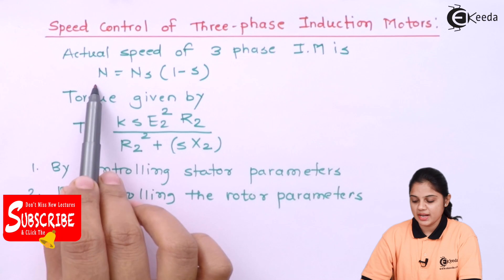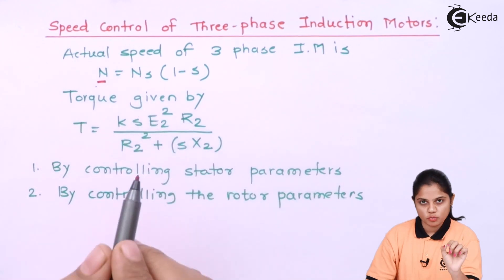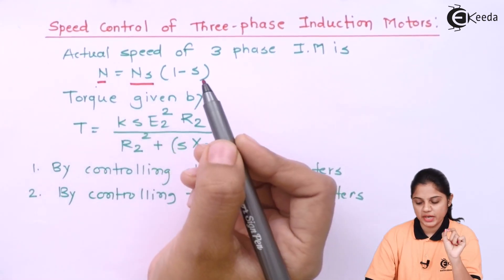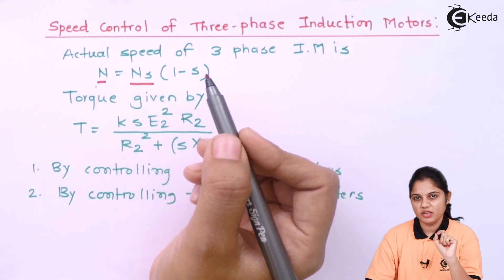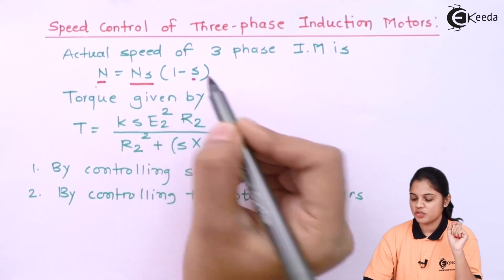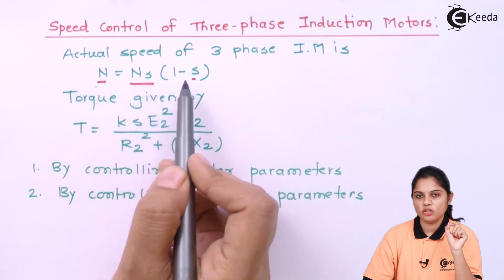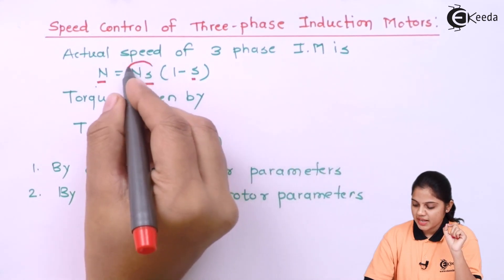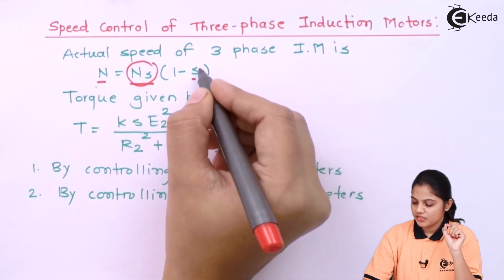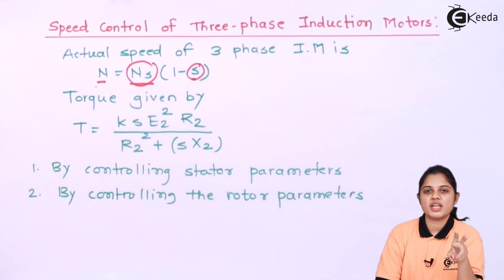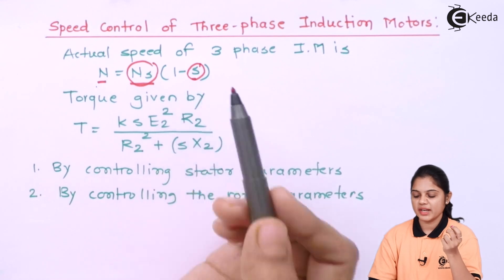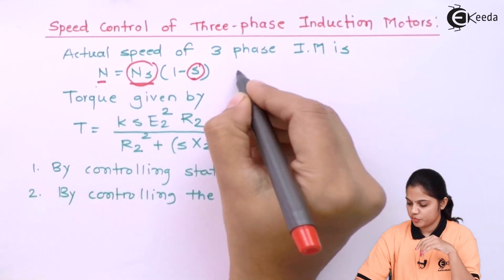The actual speed of the three-phase induction motor is given by: N = NS × (1 - S), where N is the speed of the motor, NS is the synchronous speed — that is 120F1 divided by P — which we have seen in a previous video, and S stands for slip. Now if you see the formula properly, either you can change NS, the synchronous speed, or you can change S, the slip, or you can change both parameters to change the speed of the motor. That is the first point to be noted.